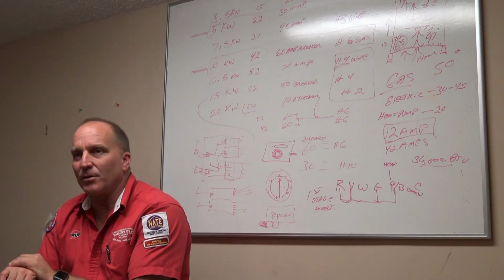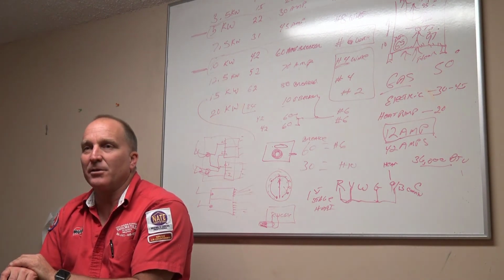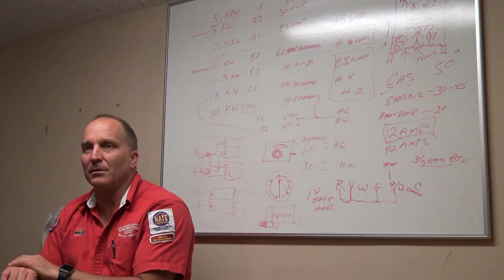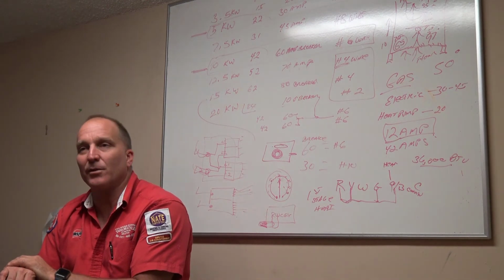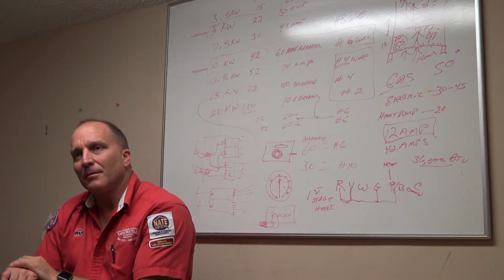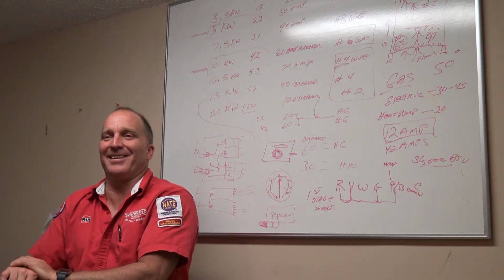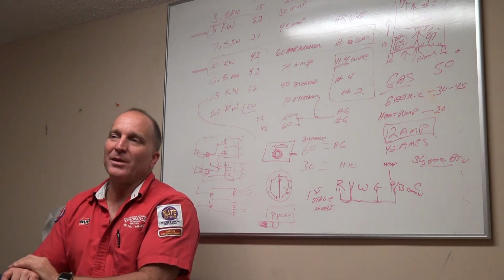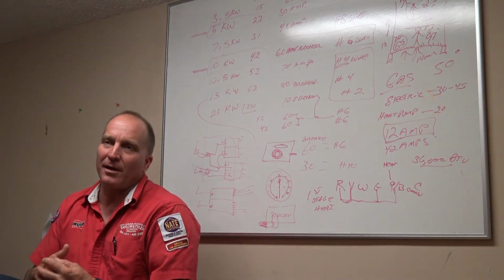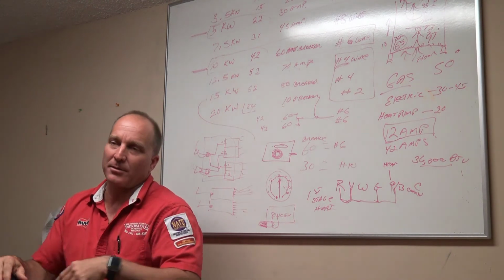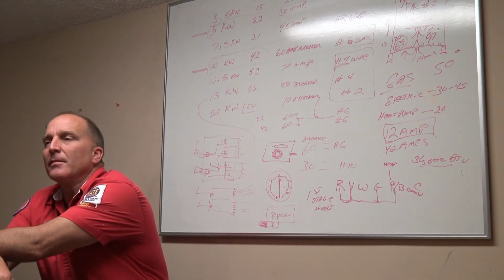I said, your static pressure? He goes, you told me I need a manometer to check static pressure if I really want to know what CFM that system's running. I'm like, yeah, that's what I told you. He goes, well, that's what I want to buy. He says, now, what do you think's wrong with it? So he would tell me what he thought was wrong with it, and I would give him my thought process on that particular deal.